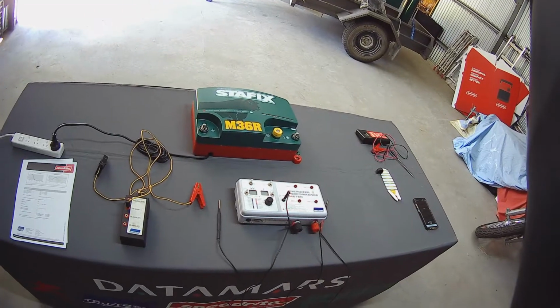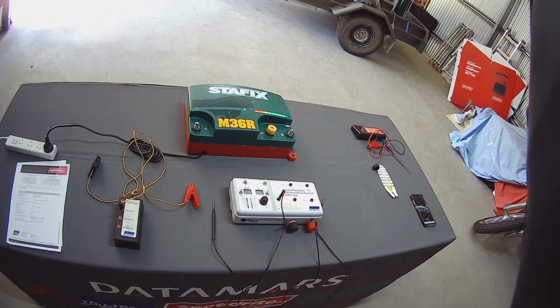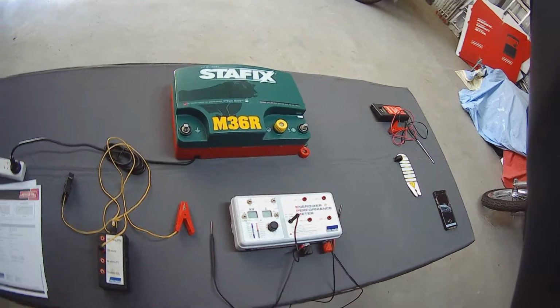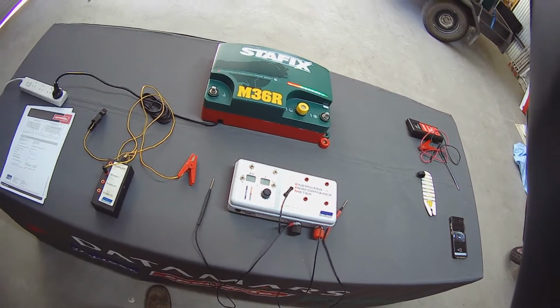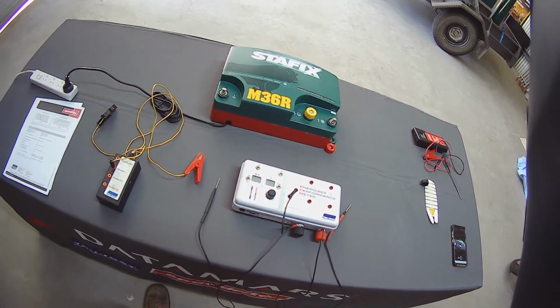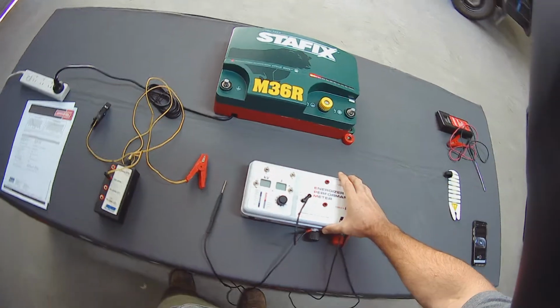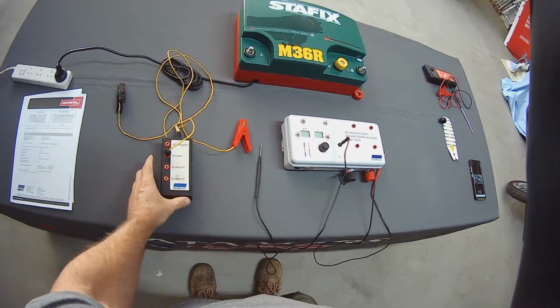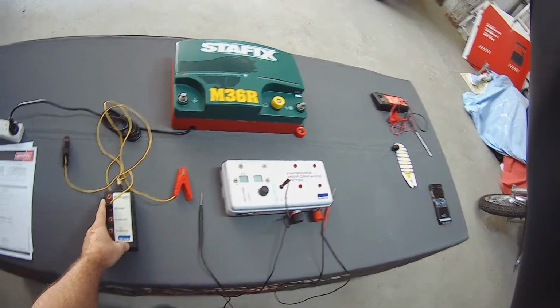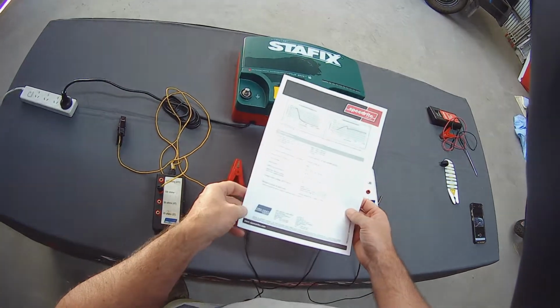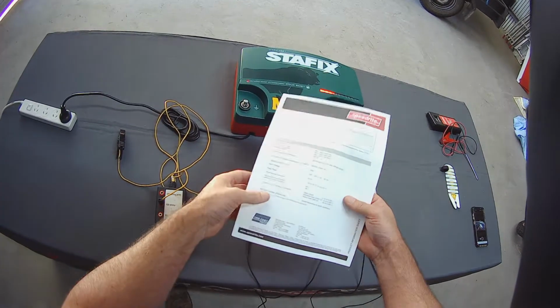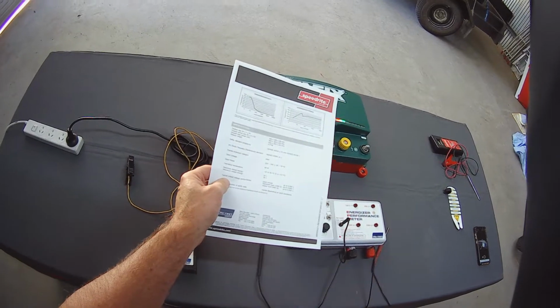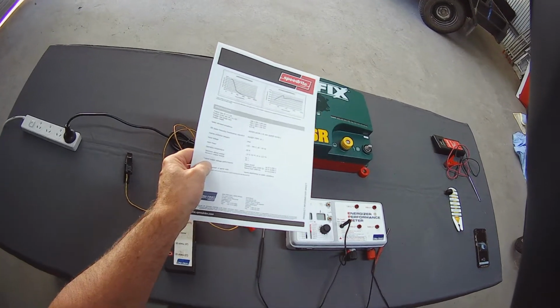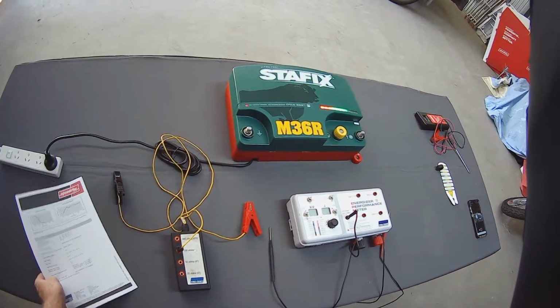In this video we're going to test an energiser, and in this case it's the Stafix M36R, which is a 36 joule output energiser. We're going to be using the Energiser performance meter, and we're going to be using the external load box. I've also printed off the tech sheet for the 36 joule energiser. In this case it's a Speedrite one, but the outputs are exactly the same, which gives us a couple of readings of what the voltage should be at certain loads.